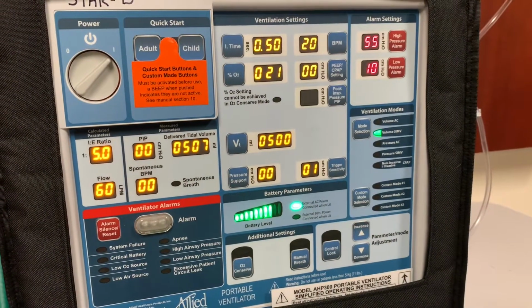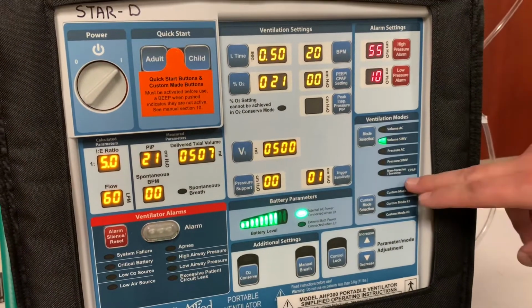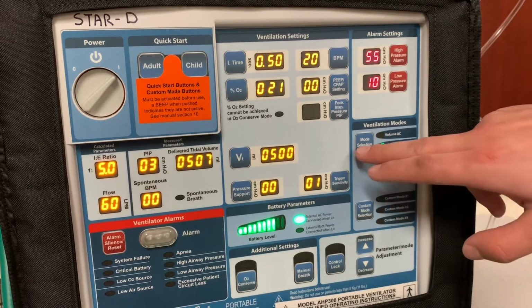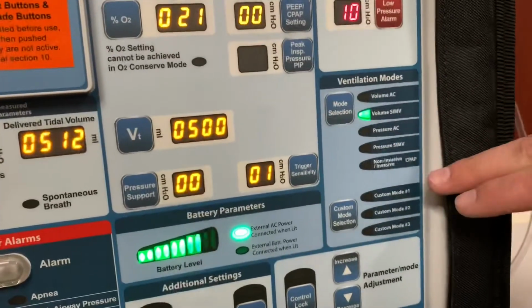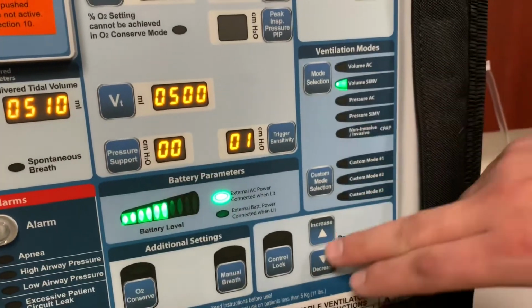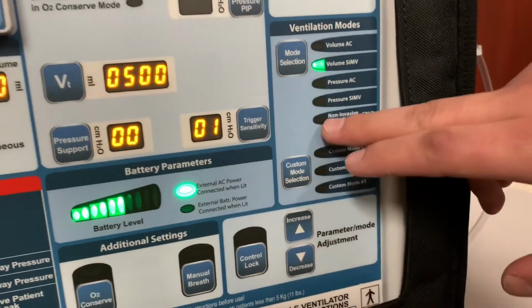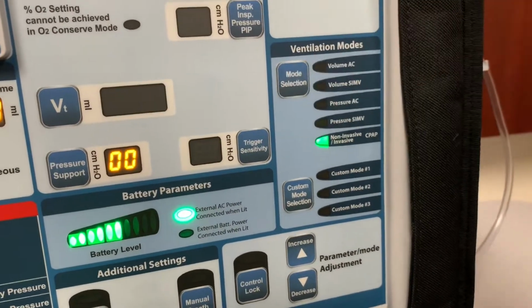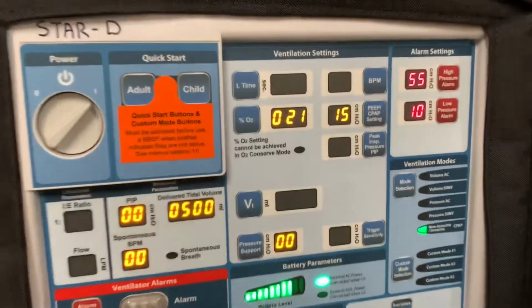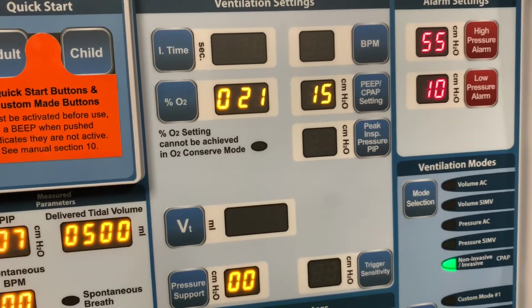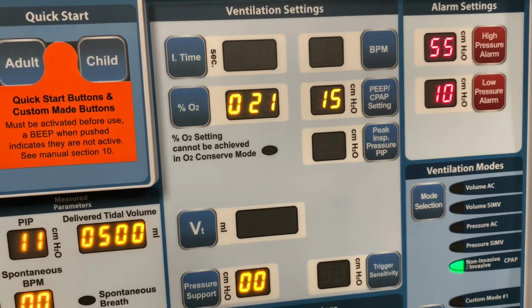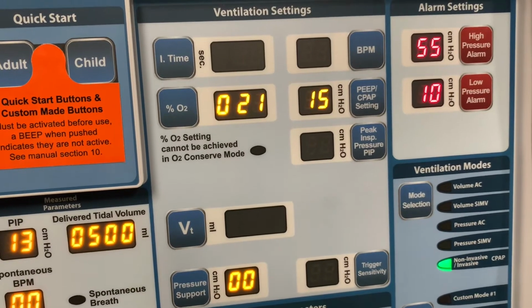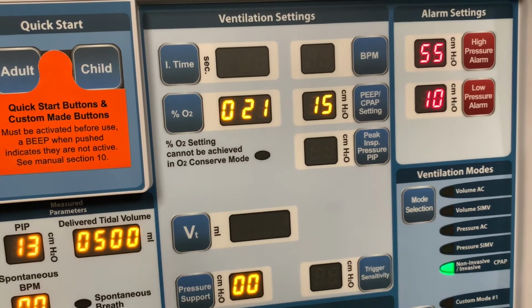Let's say that you want to change to CPAP. Just like with any of the other settings, to simply change, you need to select what you want, in this case mode selection, and you can arrow down to where it says non-invasive/invasive CPAP. Lock it in. And it's now set at, once again, an oxygen percentage of 21% with 15 centimeters of water pressure for your CPAP setting.